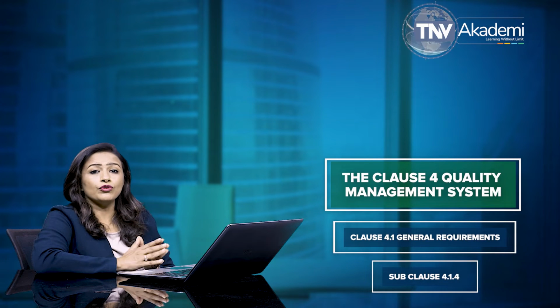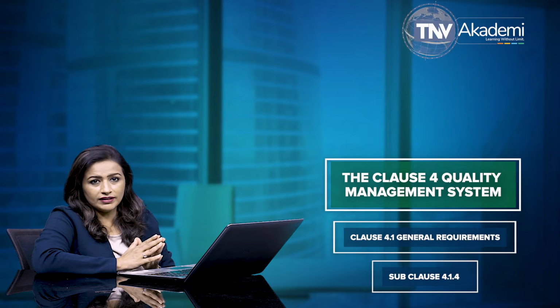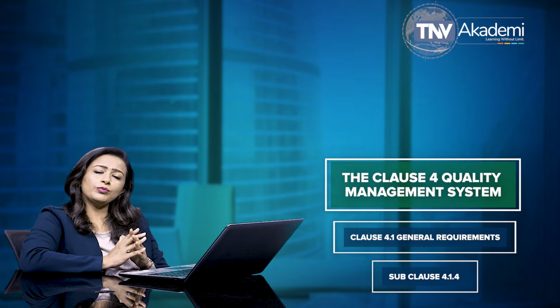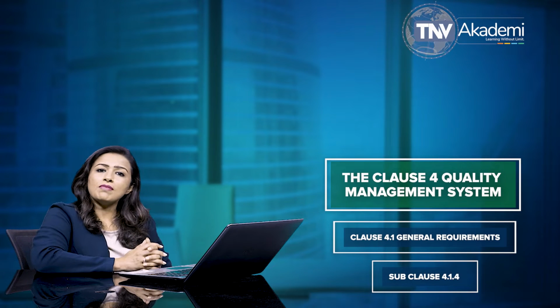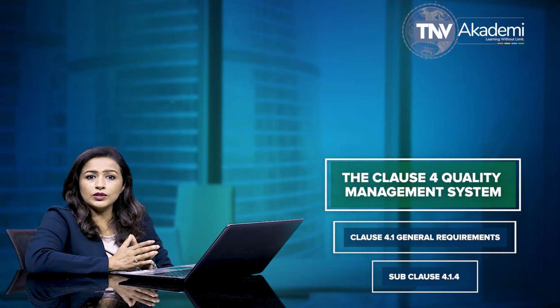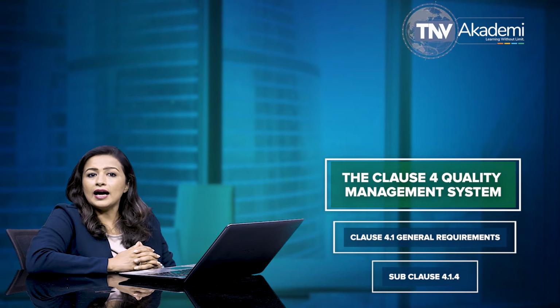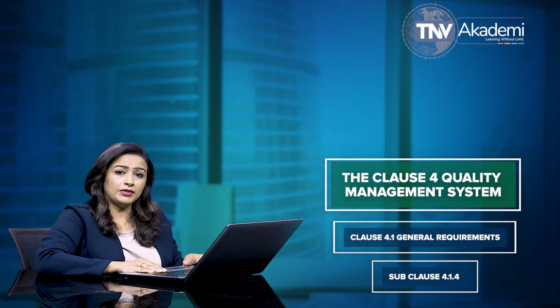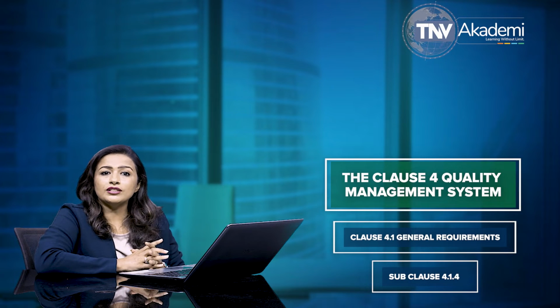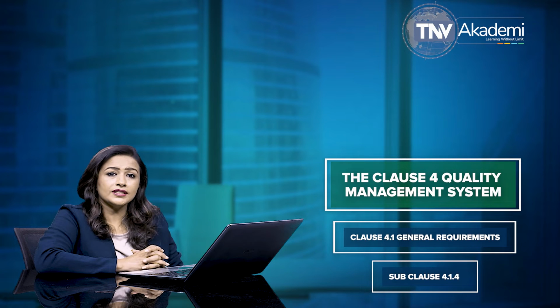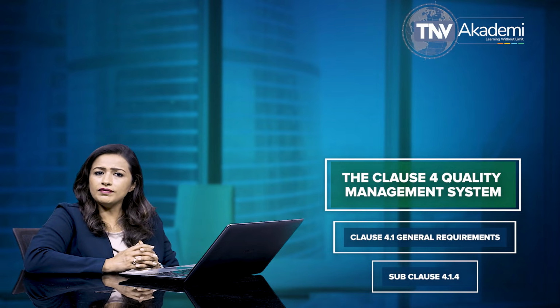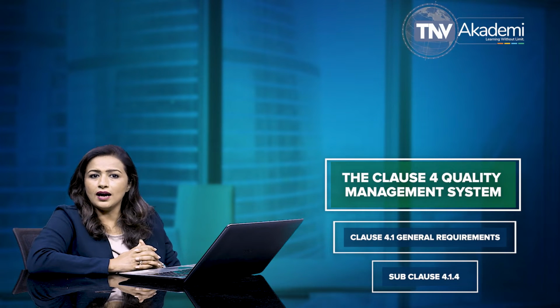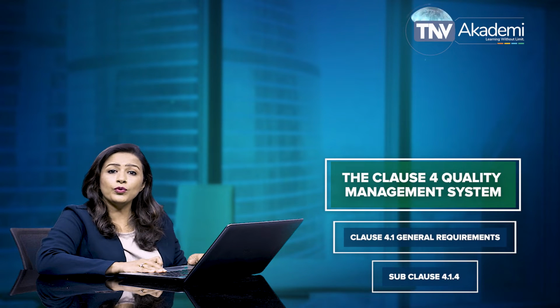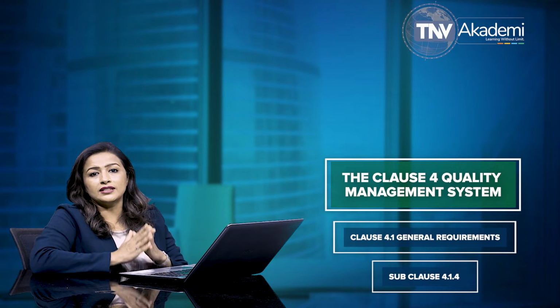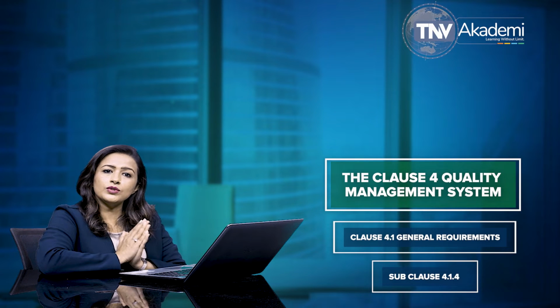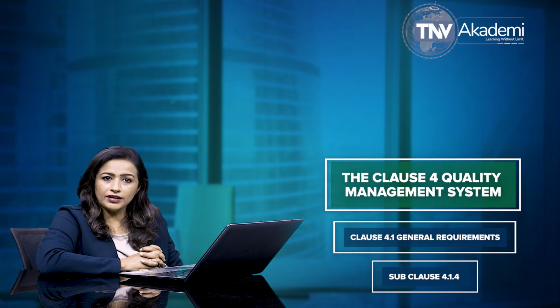Let's talk about the subclause 4.1.4 of ISO 13485-2016. The subclause 4.1.4 states that the organization is required to manage these quality management system processes in accordance with the requirements of this international standard and applicable regulatory requirements. Changes to be made to these processes are required to be evaluated for their impact on the quality management system. This clause says that changes to be made to these processes are required to be evaluated for their impact on the medical devices produced under this quality management system. This subclause 4.1.4 specifies that changes to be made to these processes are required to be controlled in accordance with the requirements of this international standard and applicable regulatory requirements.